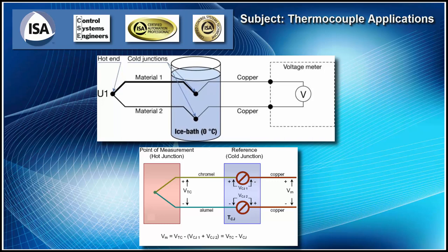All right, but when we get into our, say, temperature measurement device, a recorder, something like this, it's important to understand that this reference junction has to be referenced to the temperature of the building or where the measurement device is. And typically we'll put on a 500 ohm reference resistor. And this will tell us what the temperature is by measuring that resistance. We know what the temperature is in the building, so we can calculate an accurate temperature to subtract from this thermocouple.